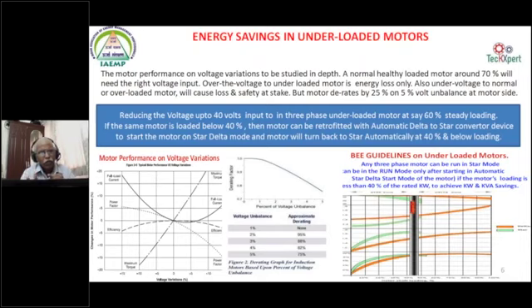Instead of operating the motor at 420 volt, if you have a servo stabilizer or anything set for the motor, or you have a batch of motors all operating at only 50%, then you can even reduce the tapping of the transformer from 420. You can bring it to 400, or you can bring it to 380 also. Because at 60% loading, I don't say it's totally underloaded, the motor can afford to have 380 volt and still it will give a lot of energy savings, as the energy consumption is going down for this given loading.